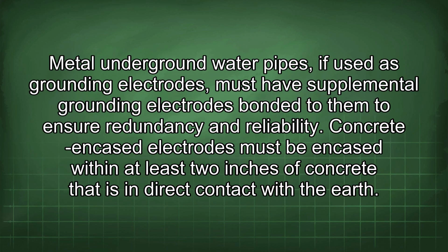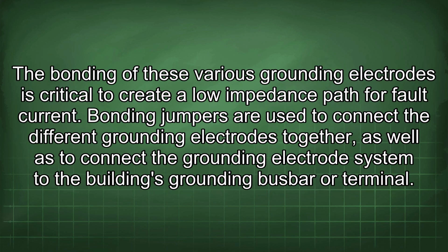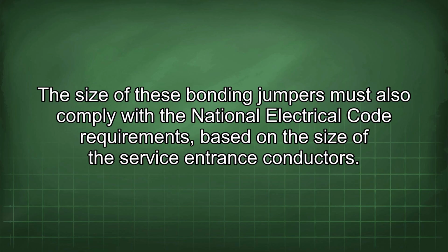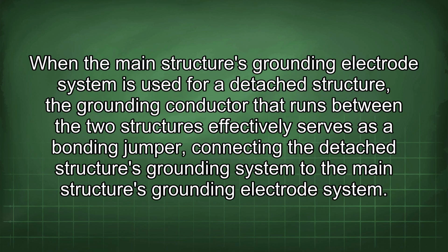Metal underground water pipes, if used as grounding electrodes, must have supplemental grounding electrodes bonded to them to ensure redundancy and reliability. Concrete encased electrodes must be encased within at least 2 inches of concrete that is in direct contact with the earth. The bonding of these various grounding electrodes is critical to create a low impedance path for fault current. Bonding jumpers are used to connect the different grounding electrodes together, as well as to connect the grounding electrode system to the building's grounding busbar or terminal. The size of these bonding jumpers must also comply with the National Electrical Code requirements based on the size of the service entrance conductors. When the main structure's grounding electrode system is used for a detached structure, the grounding conductor that runs between the two structures effectively serves as a bonding jumper, connecting the detached structure's grounding system to the main structure's grounding electrode system.